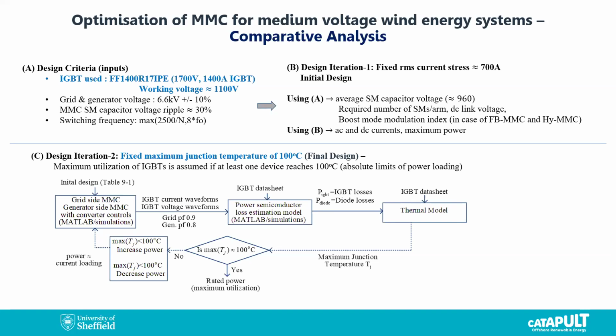For the two-level converter, we only looked at a low voltage 690 volt grid. For the MMC, we looked at a medium voltage grid, 6.6 kilovolt. What we did was push as much current through those devices as possible for a given topology, looking at the hottest device until it reaches the maximum junction temperature of 100. That was for us the indication of the maximum it can reach. Yeah, so next one.